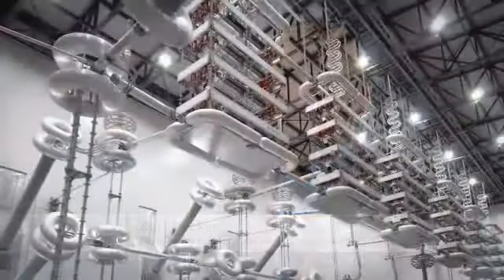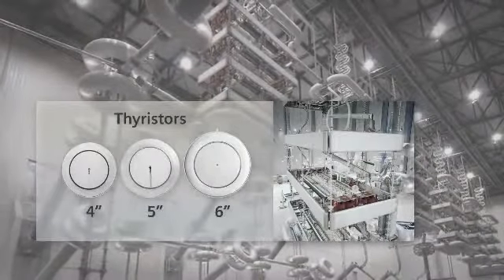The basic principle of operation of an HVDC system is the conversion of AC to DC and vice versa through converter valves. Advanced power electronics are the key. The converter stations link the HVDC transmission line to the AC systems at the power generation facility and in the load center. This way it becomes possible to bridge distances of 1,200 miles and more and get the power to exactly where it is needed.